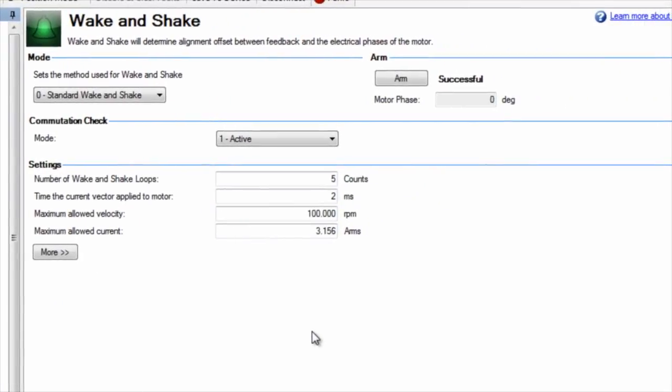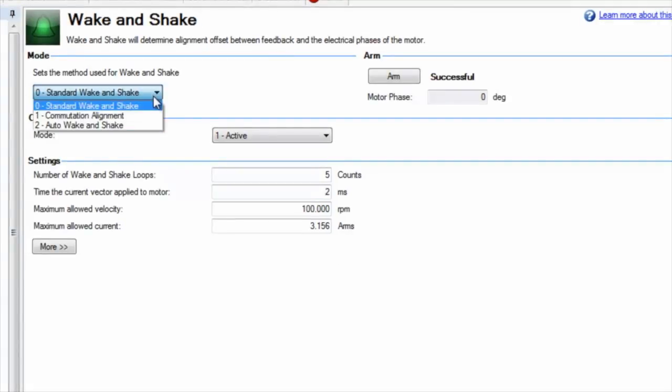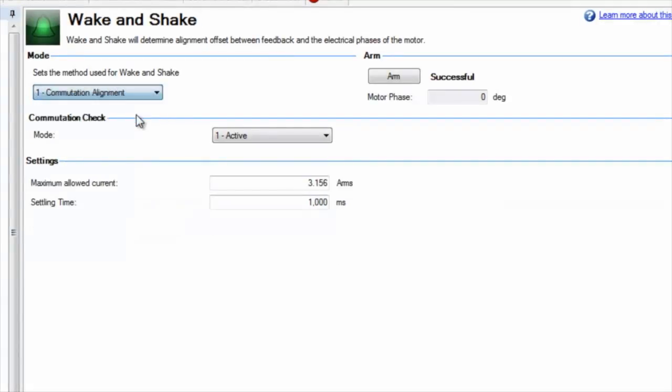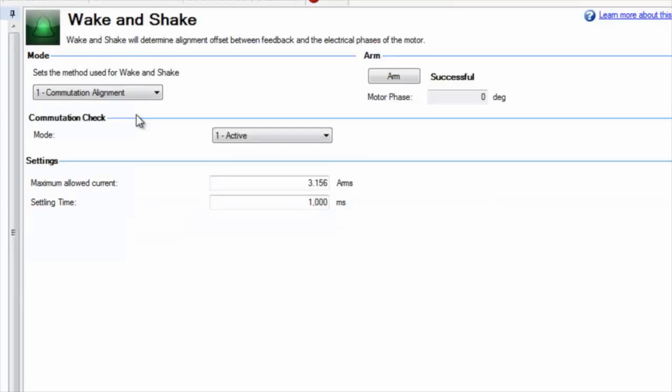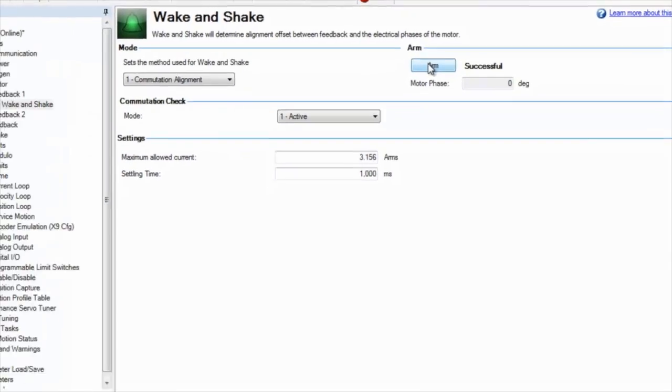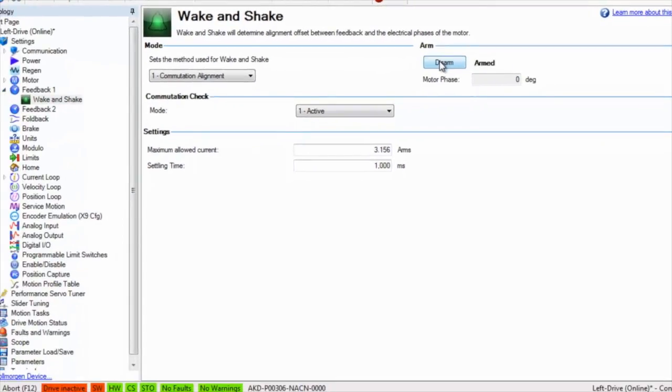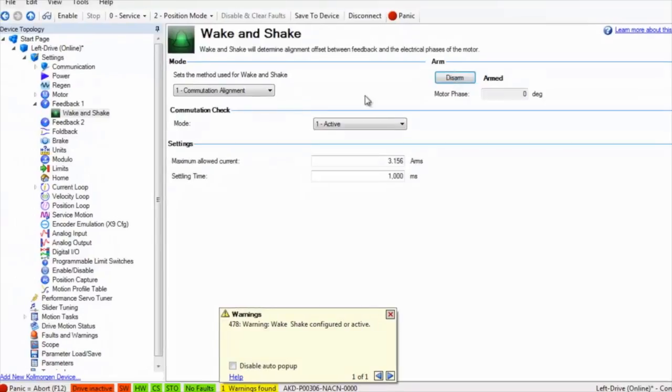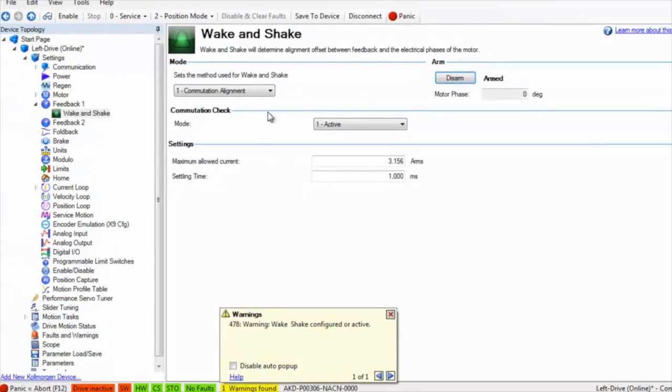Expand feedback 1 to show the tab for wake and shake. In our example, the motor has a sine encoder feedback, so the proper mode will be commutation alignment. Select 1, commutation alignment, from the mode tab.